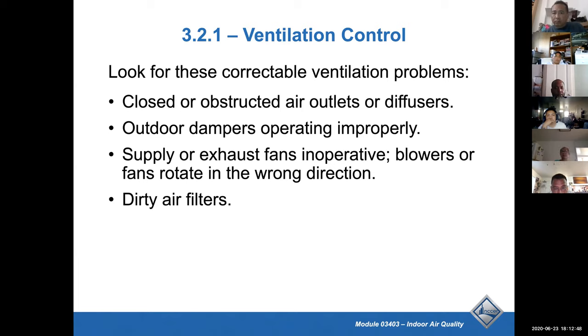Ventilation control. Okay. Closed or obstructed air outlets or diffusers, outdoor dampers operating improperly. I actually saw one building where the outdoor dampers were frozen in the shut position. Rusted, actually shut. Supply exhaust fans inoperative. I've seen that too. And dirty air filters. Oh, I definitely see that.